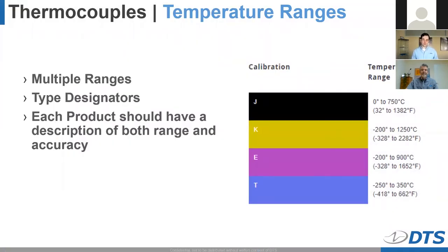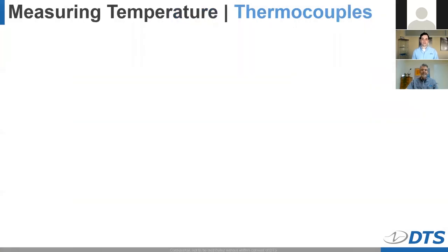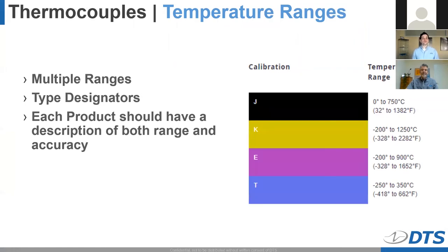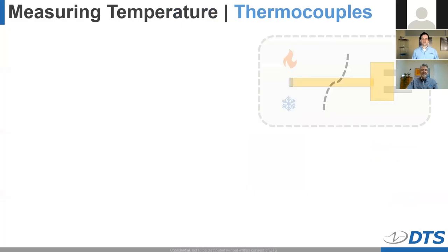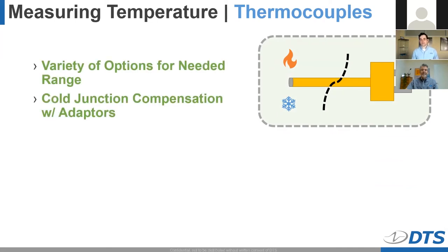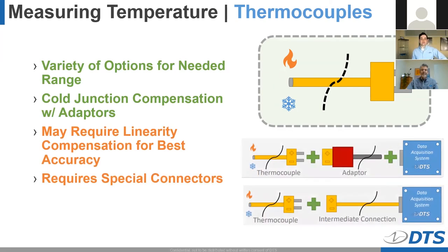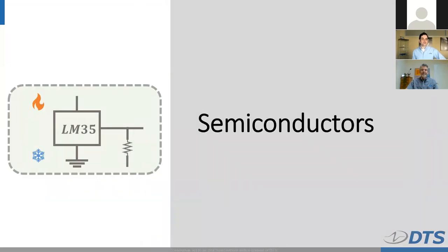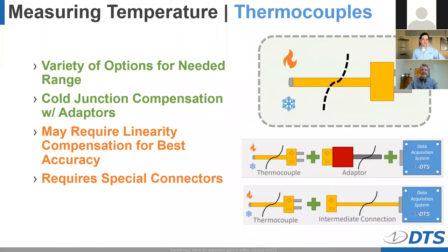One of the great advantages of thermocouples is the wide range of classifications based on the temperature range they can accurately cover. If you go to a manufacturer site like Omega, they will break down the types of thermocouples and corresponding ranges. In this table I've shown the common types — K being one of them, but J, E, and T are also displayed. Some main points with thermocouples: they have a good range for different temperatures. The cold junction effect can be easily accounted for with adapters. It may be necessary to have linearity compensation, and it's possible you'll need special connectors.